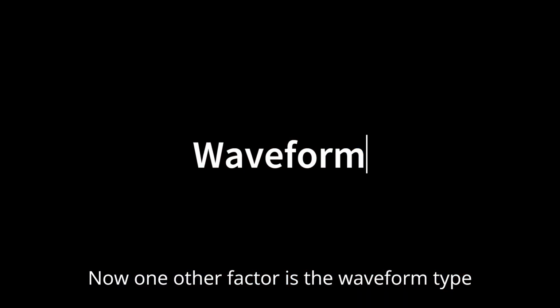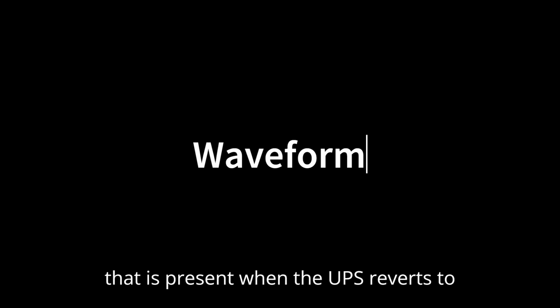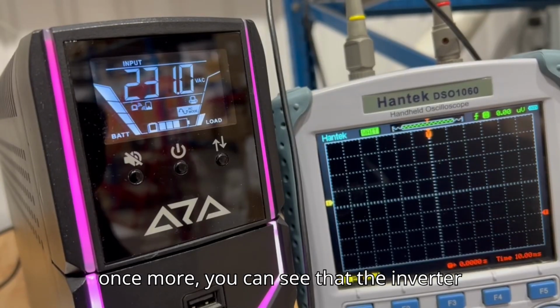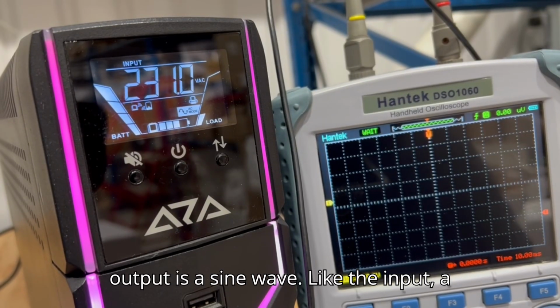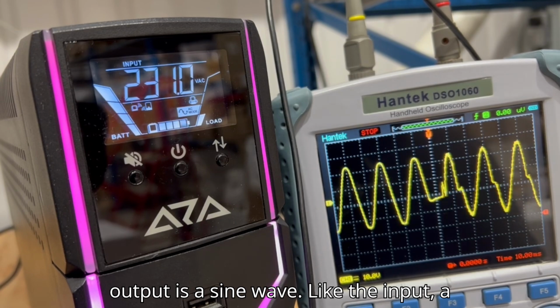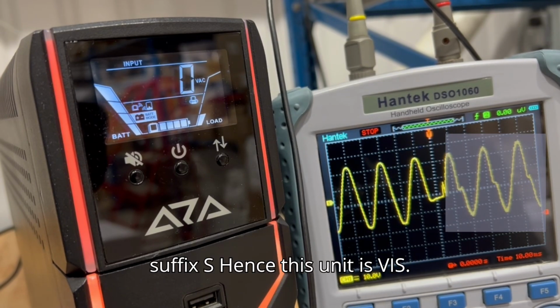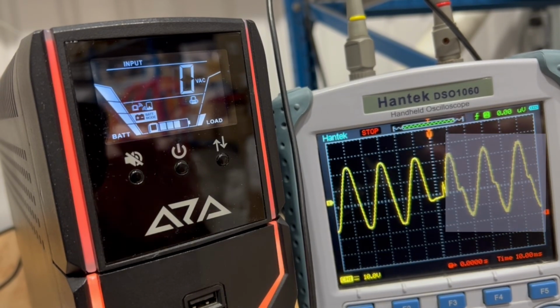Now one other factor is the waveform type that is present when the UPS reverts to battery. If I can show you the VIS output once more, you can see that the inverter output is a sine wave like the input. A sine wave output waveform is given the suffix S, hence this unit is VIS.